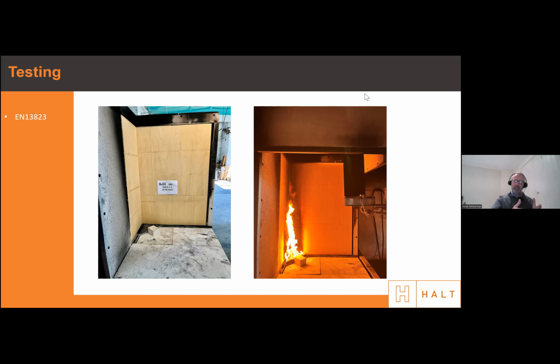Where impregnation excels over other types of reaction to fire, or surface coatings for reaction to fire, is that the material itself has the fire retardant on all surfaces. It's also been tested at the correct standard, and therefore when you have a product on site, you have a lot more flexibility with it, and it will behave on all four sides of that timber the same as it would on the side exposed to flame.